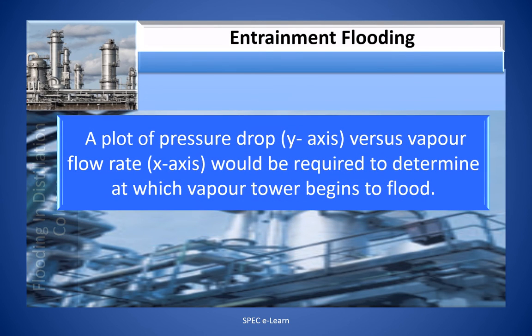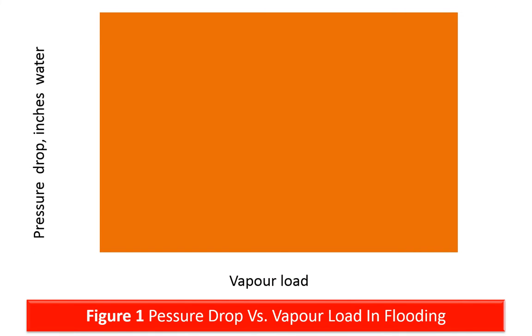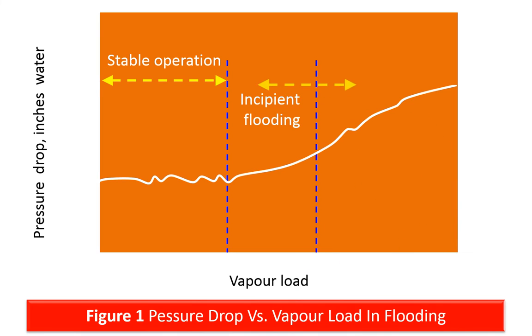A plot of pressure drop versus vapor flow rate is required to determine at which vapor flow rate the tower begins to flood. This is a typical pressure drop curve obtained when tracking the trend of increasing pressure drop against vapor load as the tower floods. There are three zones in this graph: the first zone is a stable operation zone, the second zone is an incipient flooding zone, and the third zone is a flooding zone where column flooding is taking place.